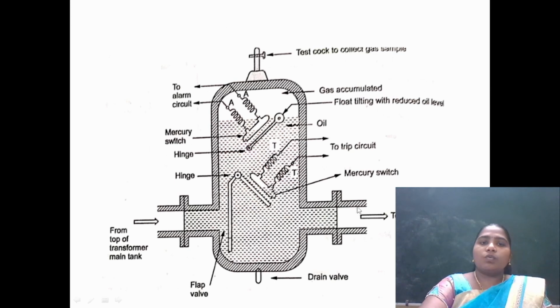And next, this is the working diagram of a Buchholz relay. Here it is completely filled with oil, and you have two mercury switches. One is connected with the upper part and the other is connected with the lower part. In this diagram we know that two mercury switches are present. One is a hinged hollow float and the other is a hinged flap valve. The hinged hollow float is connected in the upper part, attached to a mercury switch, and in the lower part there is a flap valve which is also connected to a mercury switch.